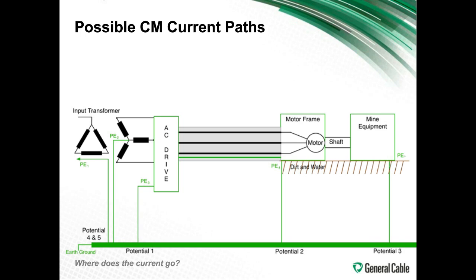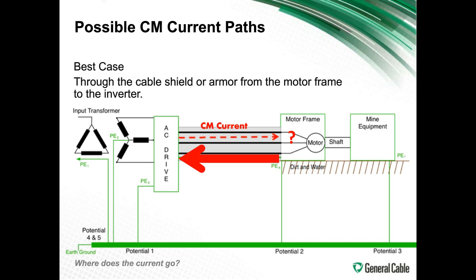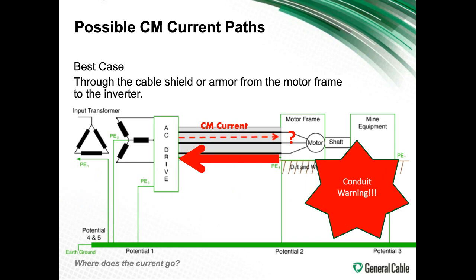The best case situation with a common mode current is to have it go back through the shield of the cable. If you can have it go back through the shield or armor from the motor frame to the inverter through the cable shield, you have to have a very well-designed cable for it to do that. That's the best case. You don't want to use a conduit as the shield, however.